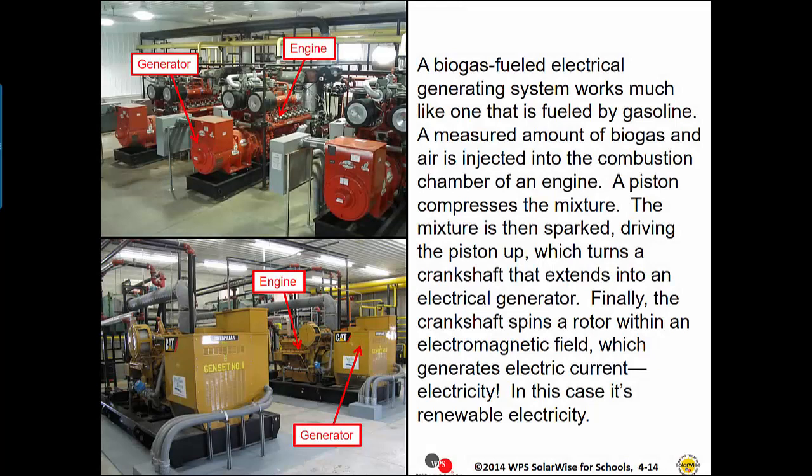A biogas-fueled electrical generating system works much like one fueled by gasoline. A measured amount of biogas and air is injected into the combustion chamber of an engine. A piston compresses the mixture. The mixture is then sparked, driving the piston up, which turns a crankshaft that extends into an electrical generator. Finally, the crankshaft spins a rotor within an electromagnetic field, which generates electric current — electricity. In this case, it's renewable electricity.